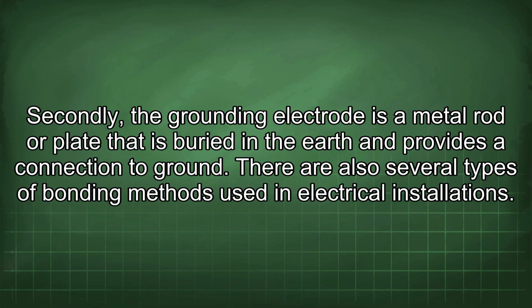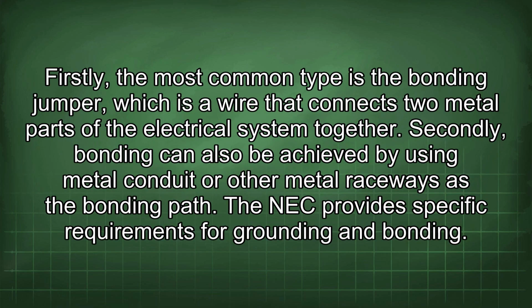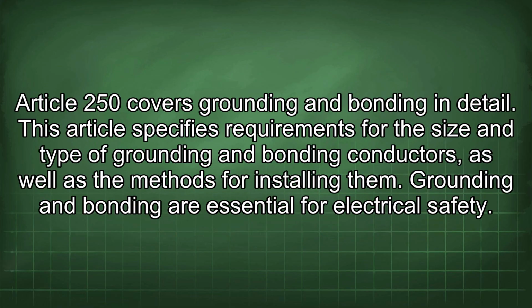There are also several types of bonding methods used in electrical installations. Firstly, the most common type is the bonding jumper, which is a wire that connects two metal parts of the electrical system together. Secondly, bonding can also be achieved by using metal conduit or other metal raceways as the bonding path. The NEC provides specific requirements for grounding and bonding. Article 250 covers grounding and bonding in detail.